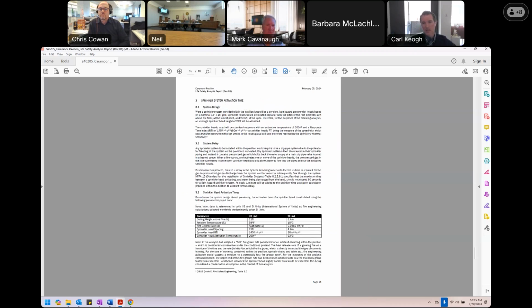The second portion is, well, how long does it take the sprinkler system to go off? Now, as we mentioned before, because it's an exterior environment, were a sprinkler system to be provided, it would have to be a dry pipe system.